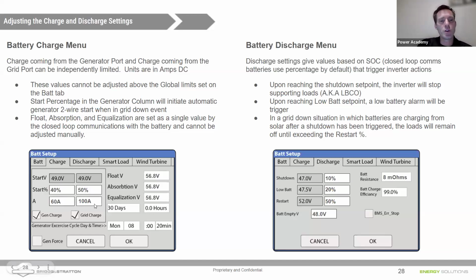or it'll trigger a charge cycle from that source if solar's not enough to charge it, or if solar's not there. On the grid charge side of things, this percentage here, if you do have a generator connected to the grid port through a transfer switch, it would use that 2-wire start. Or if you're off-grid, you might have your generator connected directly to the grid. So this is your 2-wire start signal threshold for the grid side, and this is your 2-wire start signal threshold for the generator port side. You can see that the voltages here are grayed out. Those voltages are not being used because we've told the inverter we wanted to use percentages instead of voltage.